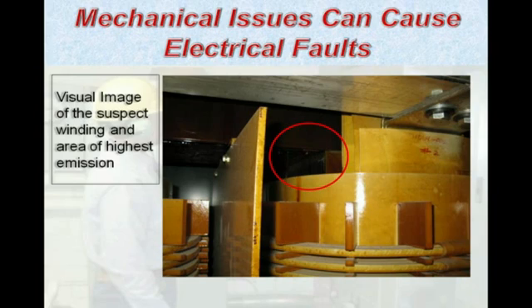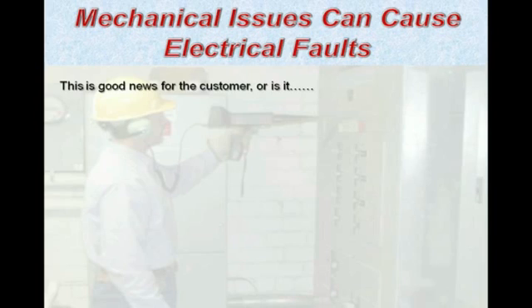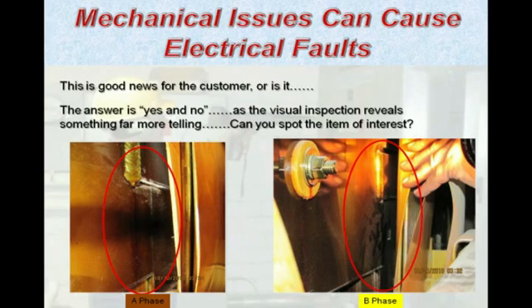Upon opening the unit, this is a visual image of where the suspect winding infrared image and recordings were made prior to the shutdown. As we get deeper into this, is it good news or bad news for the customer? Well, this is a yes and no answer based upon what was revealed. The item of interest here is what's called a miter joint, and some of you may be familiar with the construction of a transformer, but the miter joint is what joins the horizontal and vertical sections of the core within these types of transformers. So this is what we're looking at both on the A-phase coil and the B-phase coil. Now, it may be a little difficult to tell here, but there's a major difference that we're going to find out is going to be the root cause of our problem.